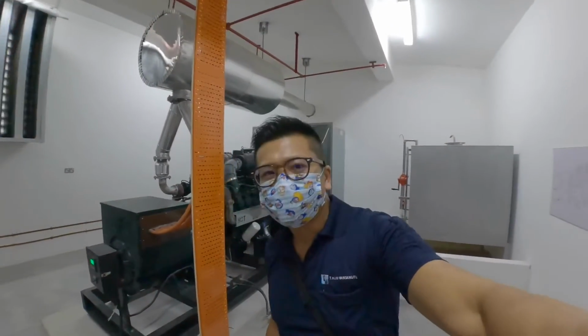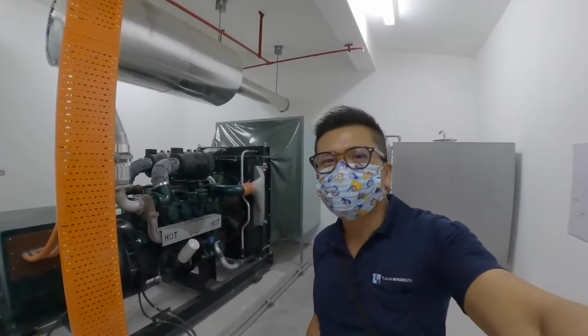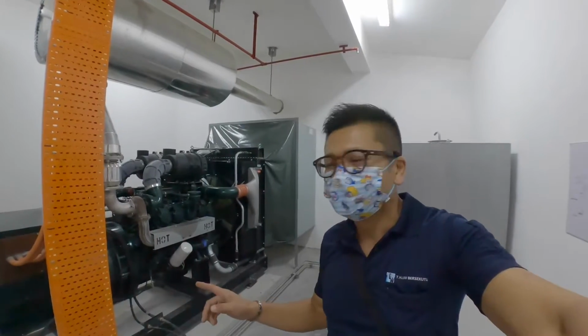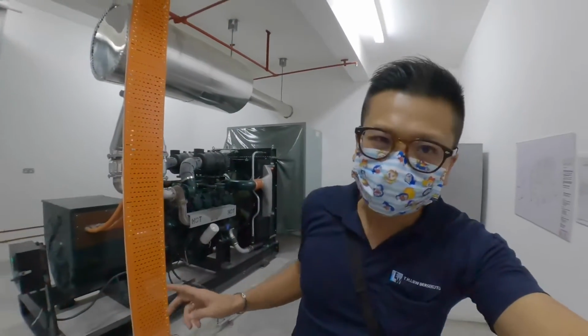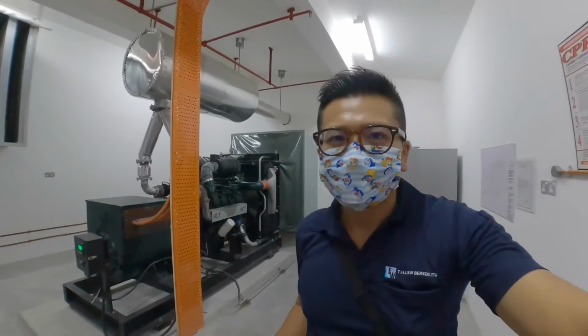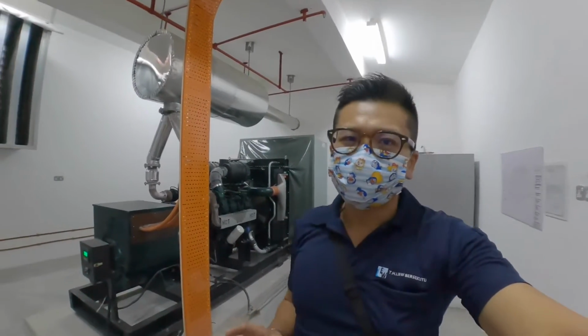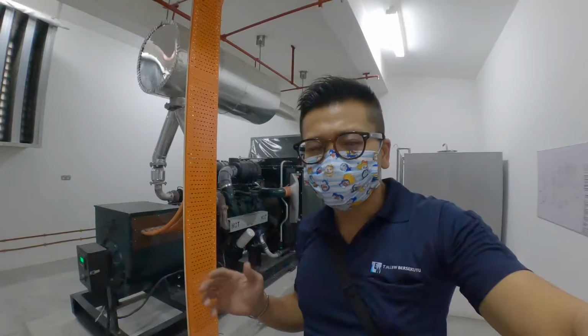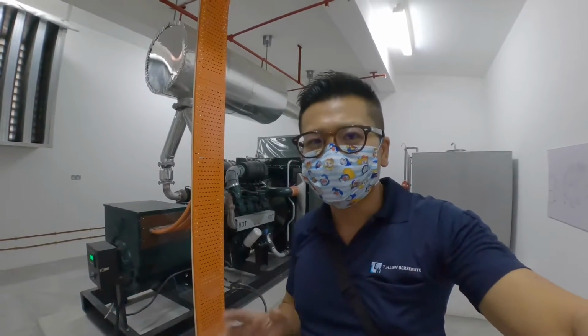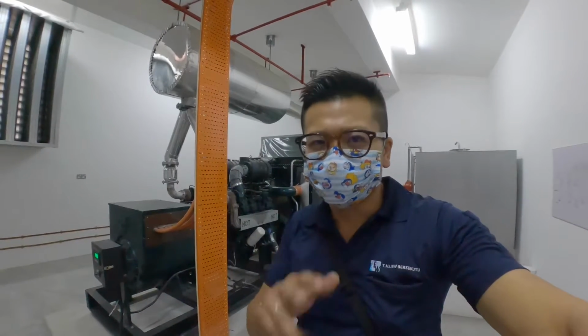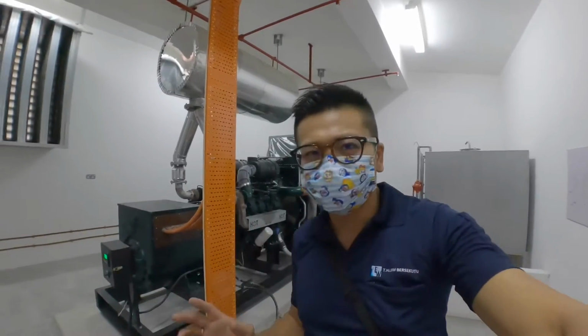Okay, today I'm at 333 Residences. This is the 333 Residences genset room. Today I'm going to start this genset under off-load condition. One purpose is to test that the genset is in good condition and is able to start and stop during a TNB power interruption. First of all, before we test run this genset, we're going to check the genset first.